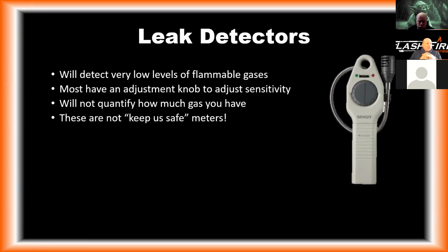Leak detectors, we'll talk about this a little today as well. A leak detector will detect very low levels of flammable gas. We will get into the numbers a little bit, not that you need to memorize it, but just so you understand the level that this can detect versus our standard LEL meter. A lot of them have some sort of an adjustment knob on them for sensitivity, but it's not going to quantify how much gas you have. So it's not going to keep us safe when we talk about whether we are going into an explosive environment or not. These meters, or detectors, are not for that. These are simply to detect the presence of any level of gas.